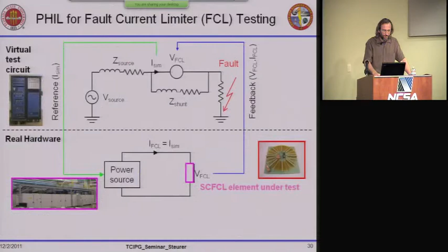Let me answer the question about power draw. Look at this here. The only power we draw from the grid, and our meter is running here, is the losses in these converters and transformers. We're shipping 500 kilowatts into the PV converter, and it ships 500 kilowatts back out, and it just circulates around. The only real power draw is in the generator test. The gearbox we procured has significant losses. At full speed, you're dealing with about 9% of a 5 megawatt rating, and those are real losses you cannot recover. But even in this case, we had about 200 kilowatts of losses at 15,000 RPM, and the 1 megawatt we shipped through the generator went right back out. It just circulates, so it's a green facility from that point of view.